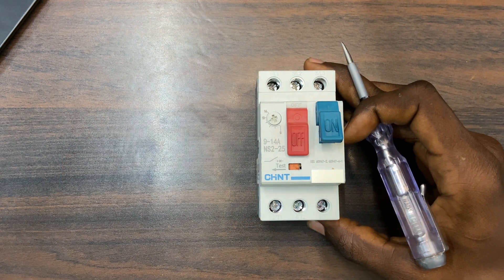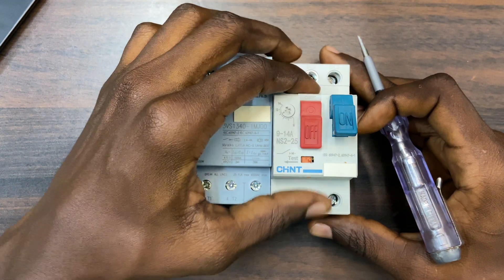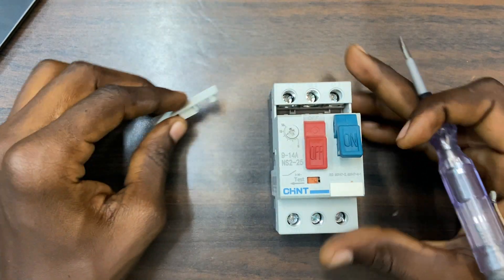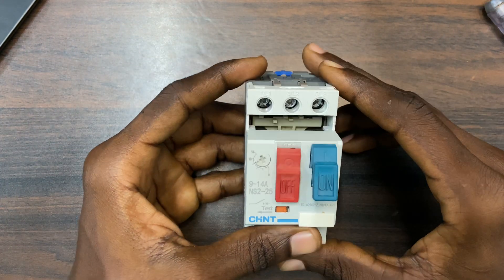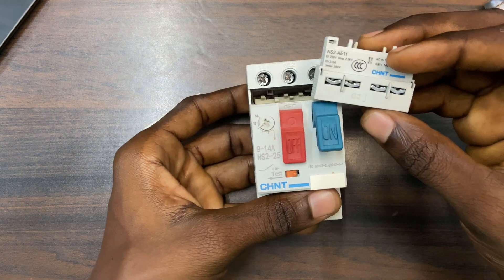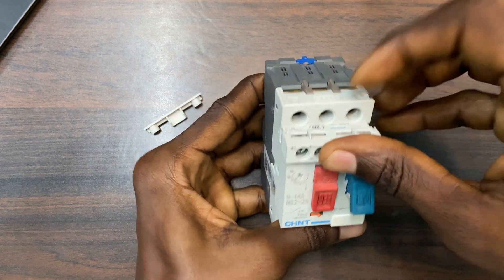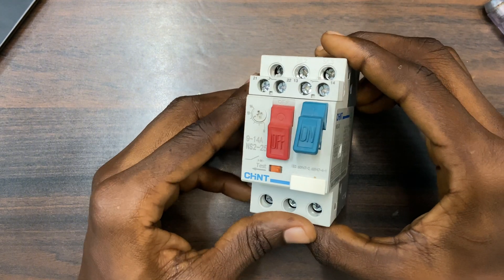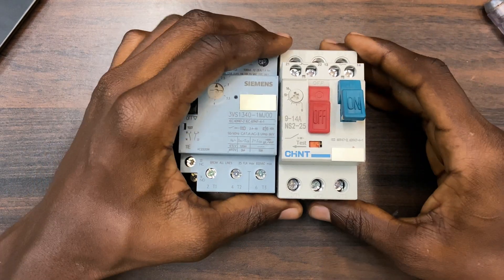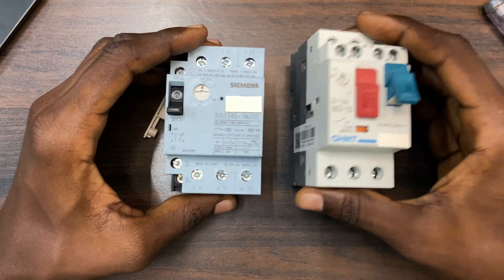As I said, we have auxiliary contacts on this MPCB, just like the Siemens type. We have the same auxiliary contact on this MPCB — you have it here. Just remove this plastic from it and you can see there is a whole space. This piece here is for an auxiliary contact block. I have one here — this is the same brand, Chint — so what I have to do is insert it. Now it has perfectly fit. Whenever you want to do trip indication, like a trip indication light, you can just use these terminals.